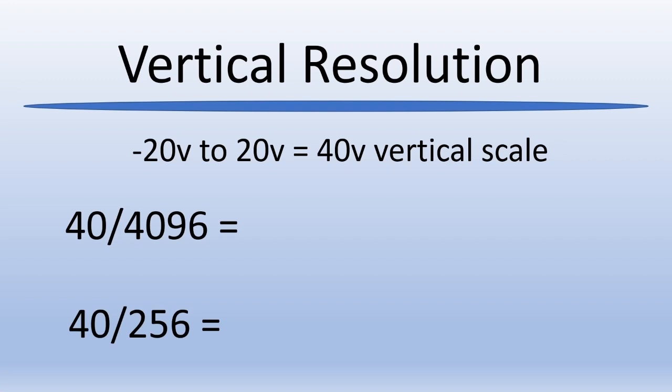I'm going to do some math here. For those of you that don't like math, it's time to go get yourself a drink. This will only take a moment, though. Consider that we typically test things between 0 and 15 volts. That would give us a division accuracy of 0.0036 volts with a 12-bit scope. Even if we set the scope to plus or minus 20 volts, 40 volts total, that still gives us an accuracy of 0.0097 volts, or a little better than 1/100th of a volt.